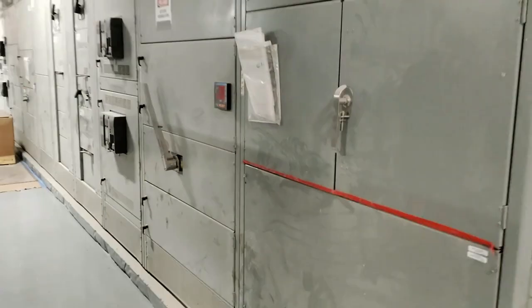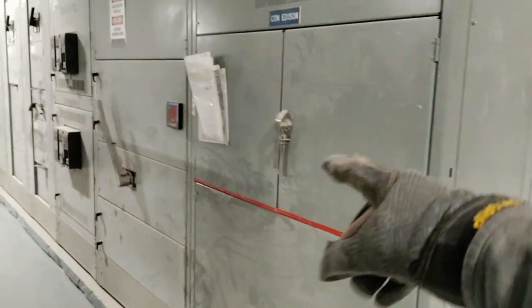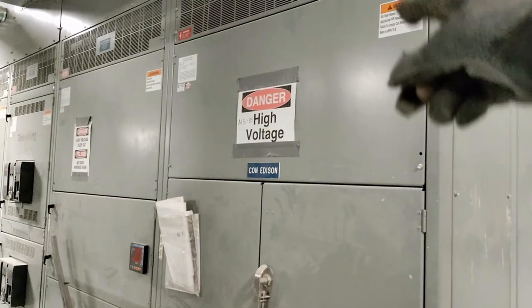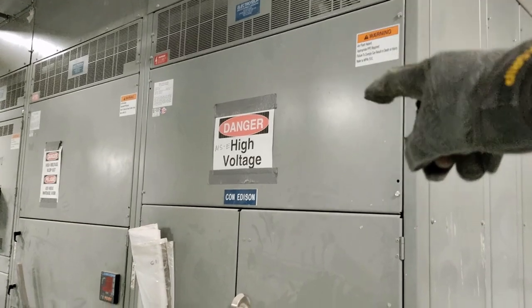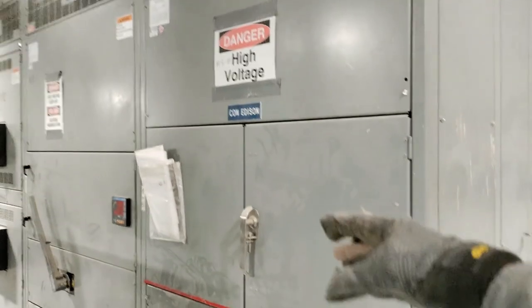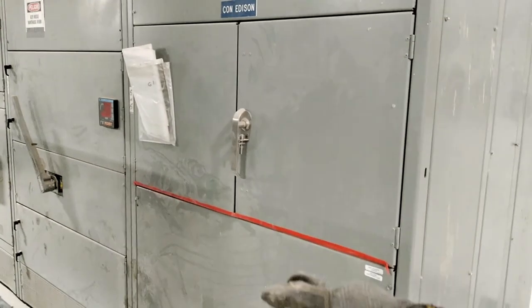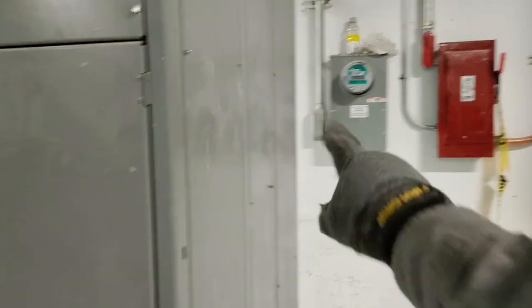So there you have it. Just so you can get a better look at it—this is my switch gear, this is where my CT cabinet is. My conductors get terminated on the top side, that's my line side. Then comes the CT, and then on the bottom is the load side—that's after the CT. The CTs are what actually go back to your meter. Let me show you one so you can see exactly what I'm talking about.